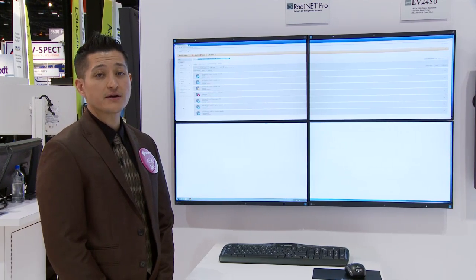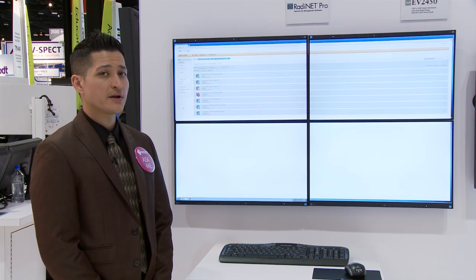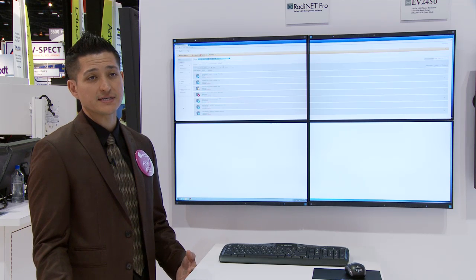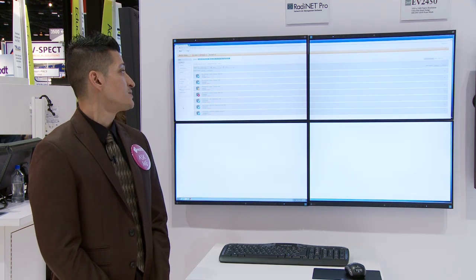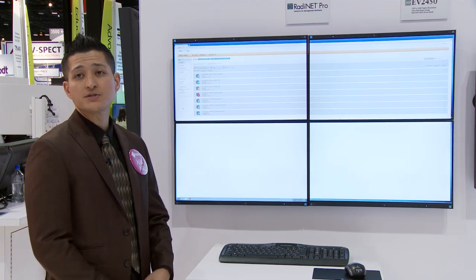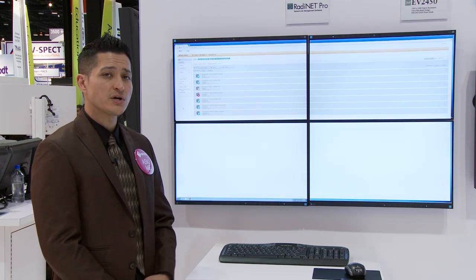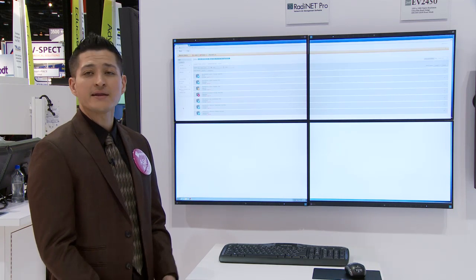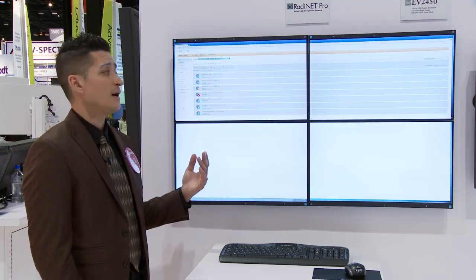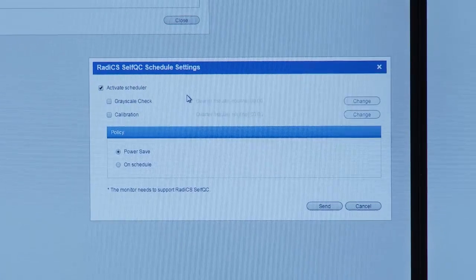Our RadiNet Pro solution is our quality control software that comes with all of our RadiForce displays. This monitor allows for one centralized administrator to oversee the entire facility's monitors and hardware. As you see here in this demonstration, we're actually doing a network throughout our booth of all the different displays to showcase exactly what it might look like in your own facility — you'd be able to see when the last time the monitor was scheduled to calibrate.